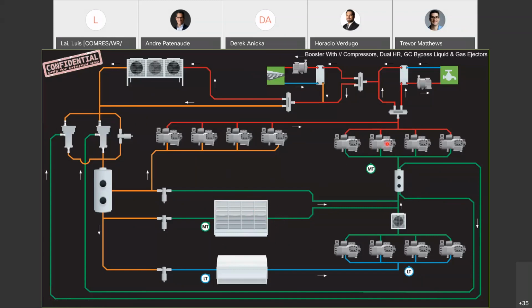That means my motor works less. That means I've got an energy efficiency gain. So by having low superheat, though, I better make sure that I've got an accumulator to trap my liquid. So that's what that's there for. I can gain efficiencies by floating up. I need a suction accumulator to trap my liquid, but once I have liquid in there, I want to try to move that liquid out of there and bring it all the way back into the front of my flash tank. So this is a liquid ejector that takes high pressure gas, siphons or draws the low pressure liquid in, mixes it, and transfers it into the flash tank.